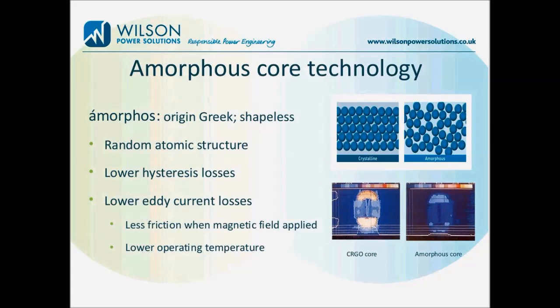So the structure of it means that less friction is created during that magnetisation, and so therefore less heat is produced, which results in those lower losses. You can see again on the infrared imagery there at the bottom where the CRGO standard core steel unit shows a far greater heat in the red colour on the left than the amorphous product on the right hand side.